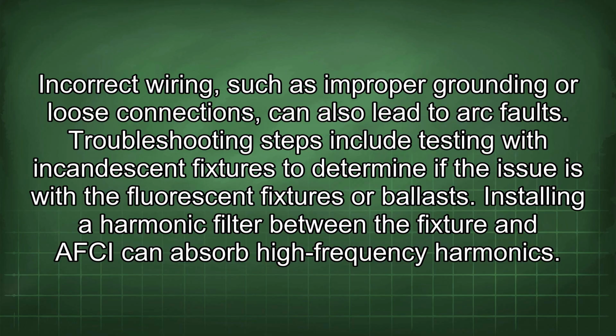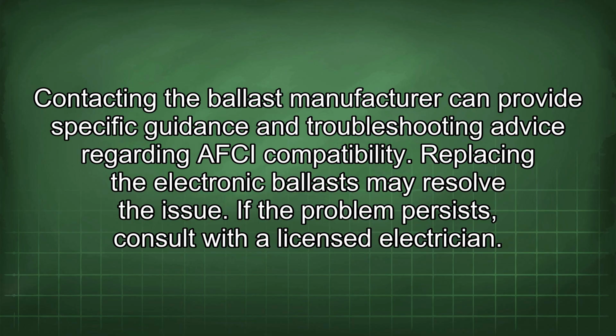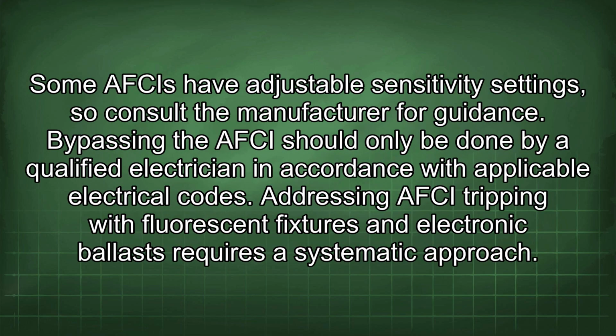Troubleshooting steps include testing with incandescent fixtures to determine if the issue is with the fluorescent fixtures or ballasts. Installing a harmonic filter between the fixture and AFCI can absorb high-frequency harmonics. Contacting the ballast manufacturer can provide specific guidance and troubleshooting advice regarding AFCI compatibility. Replacing the electronic ballast may resolve the issue. If the problem persists, consult with a licensed electrician. Some AFCIs have adjustable sensitivity settings, so consult the manufacturer for guidance. Bypassing the AFCI should only be done by a qualified electrician in accordance with applicable electrical codes.